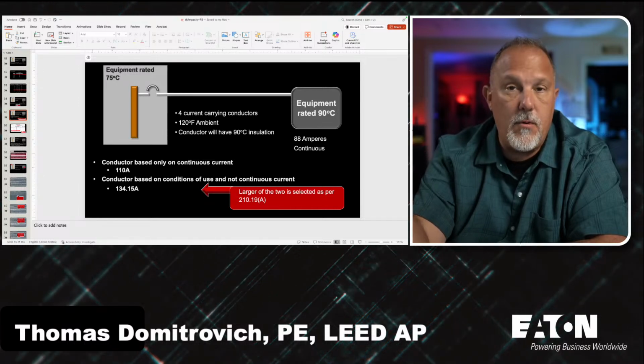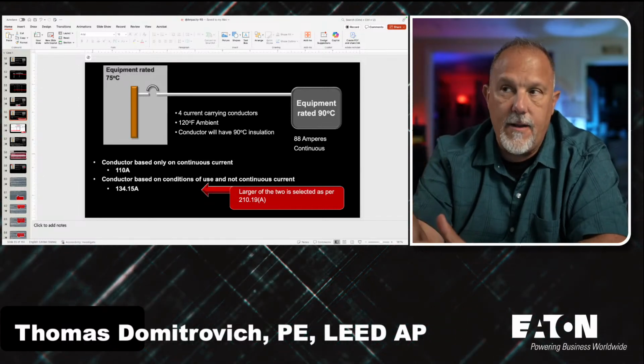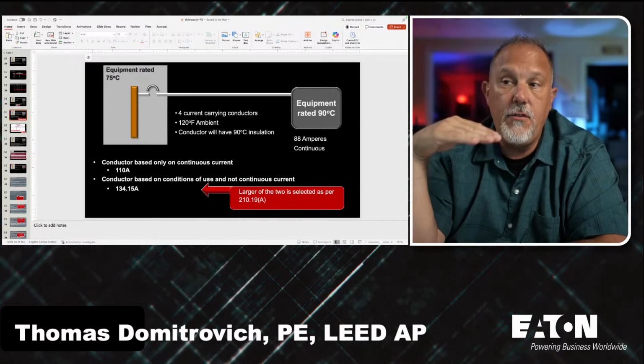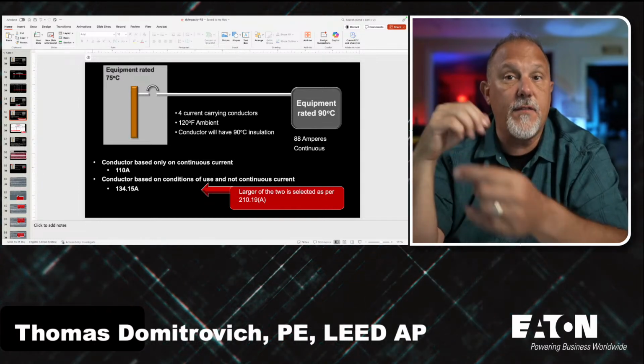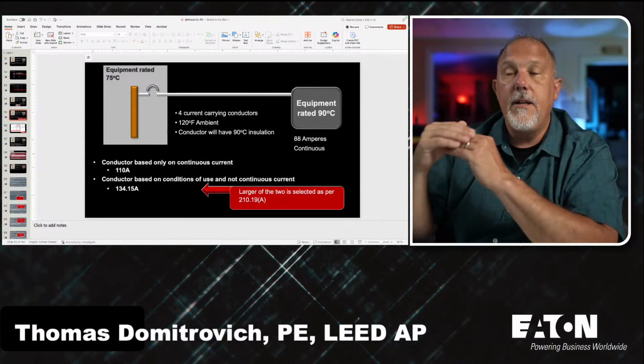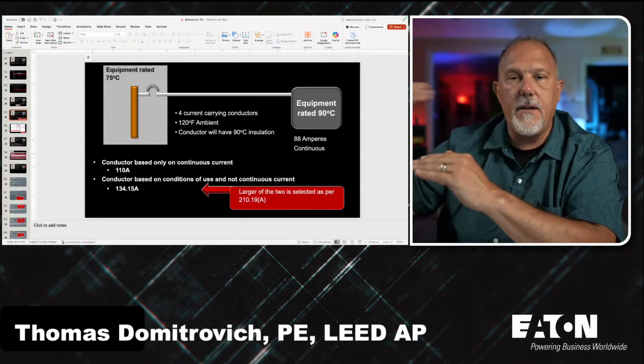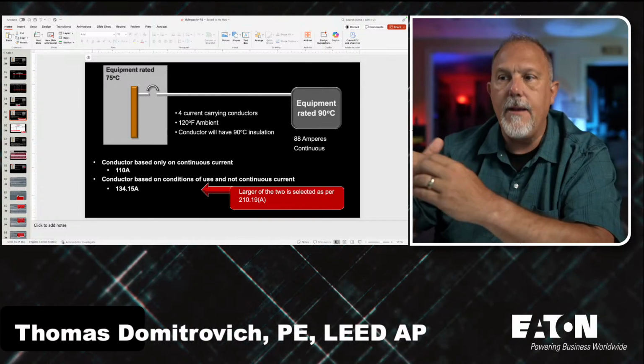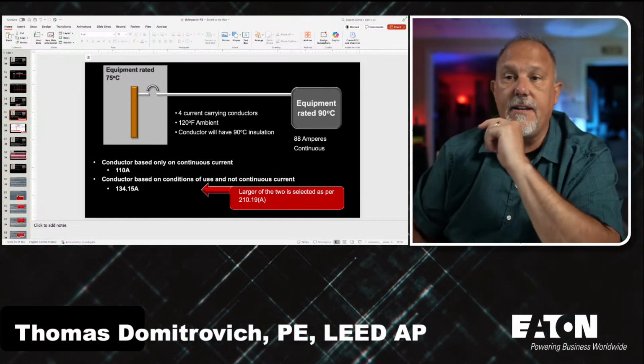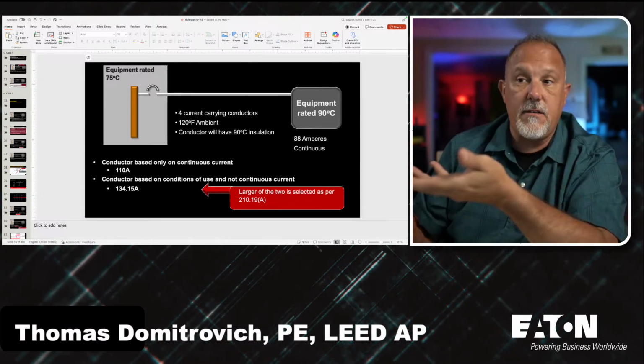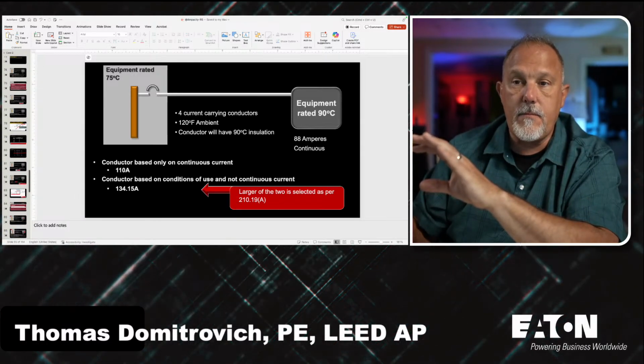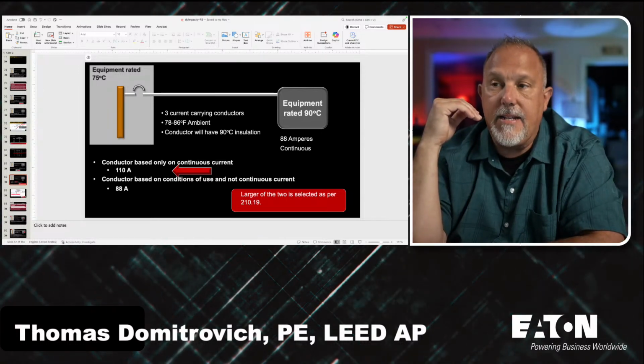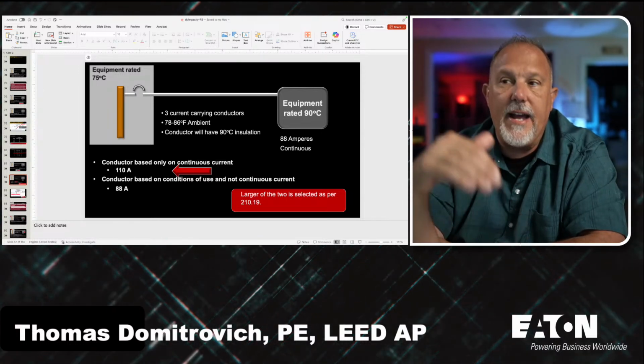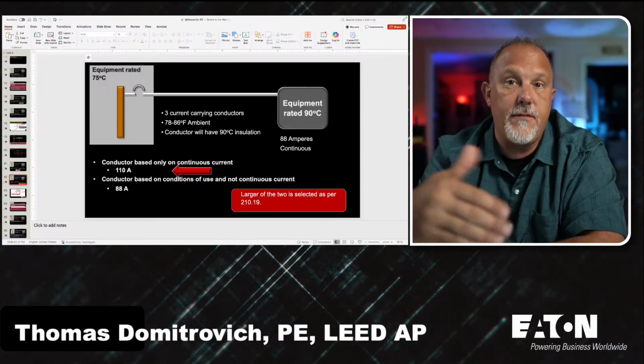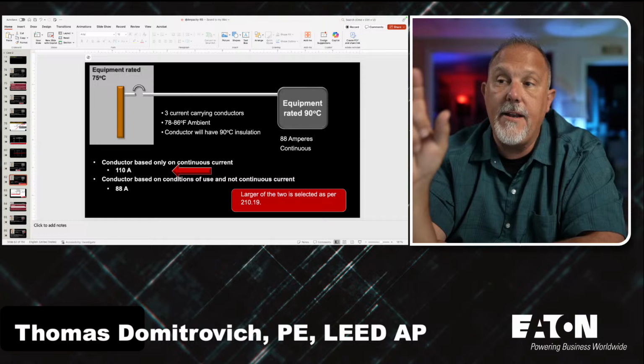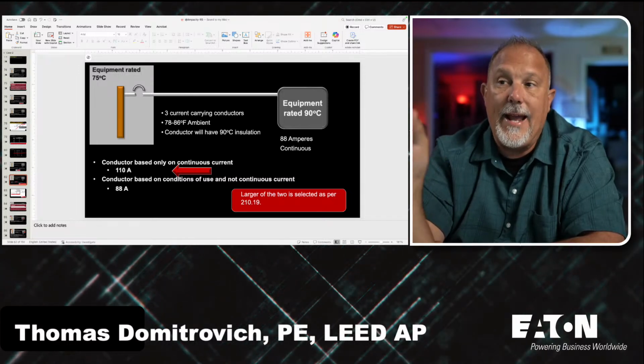For the same example, same load, my conditions of use generated a higher number because of the multiplying factors. Because of the ambient and because of the number of current carrying conductors in a raceway, I had to pick a different conductor. Now I'm just the opposite, where my continuous current times 1.25 gives me a higher number than the conditions of use. So now I know I'm at 110 amps as the minimum.